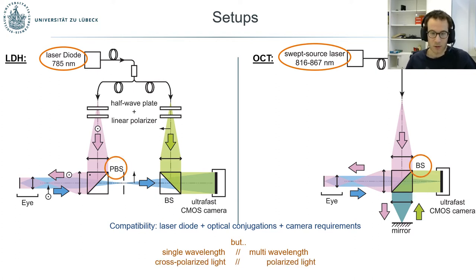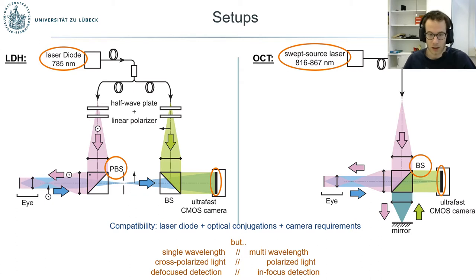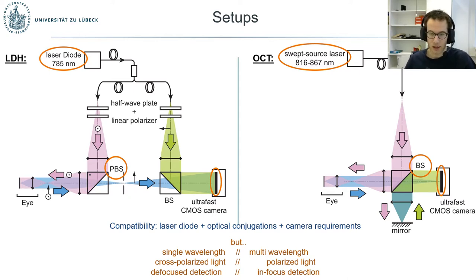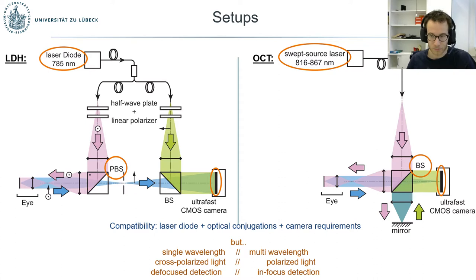LDH has so far been demonstrated with cross-polarized light to remove the specular reflection from the cornea. More importantly, LDH has been demonstrated in a defocused detection, meaning the camera is voluntarily set backward by a few centimeters so that one area of the eye is imaged over multiple pixels rather than a single pixel. This stands in contrast with OCT, which uses focused detection where one pixel corresponds to one area on the eye.